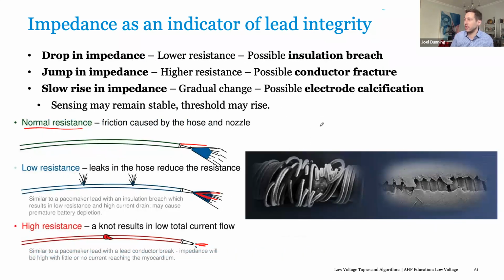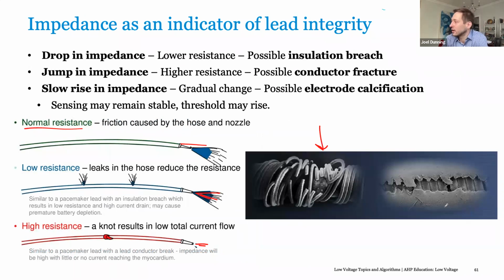I use this visualization because I think it's a really good example of a conductor failure versus an insulation breach here. Either one of these can affect the device's ability to pace and to sense over time. What you'll see sometimes with conductor failures is what are called make-break signals, where there's actually a separation, occasionally, say when the patient stretches or when the lead is stressed, causing it to not be able to capture. But then when these metal pieces unite again, it could act normally. So what you may see occasionally is inconsistent capture, but when you measure the impedance, it's within range.